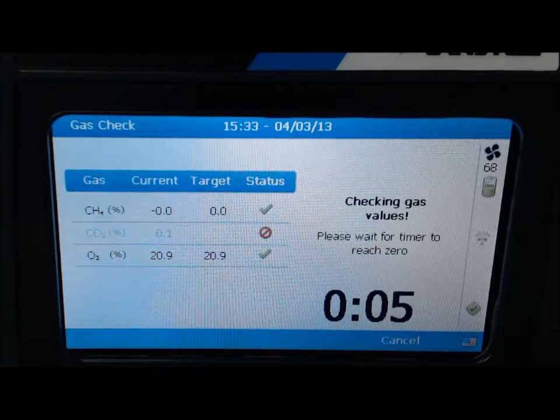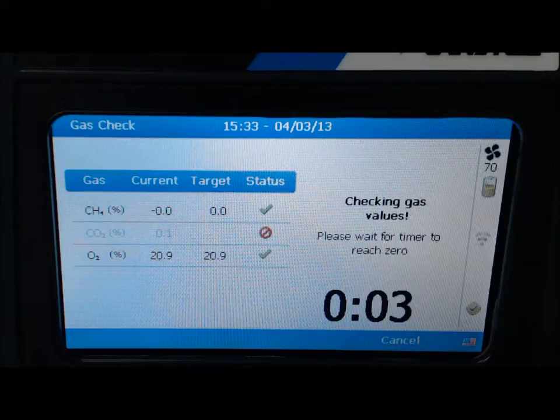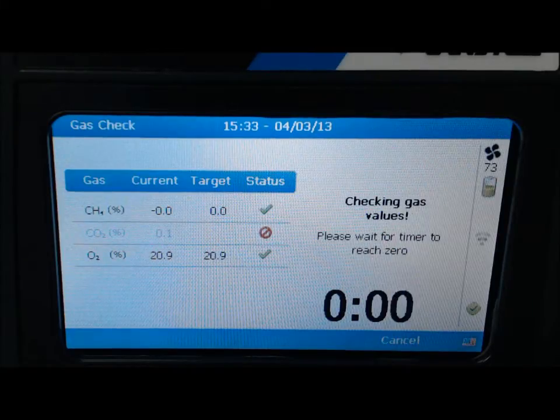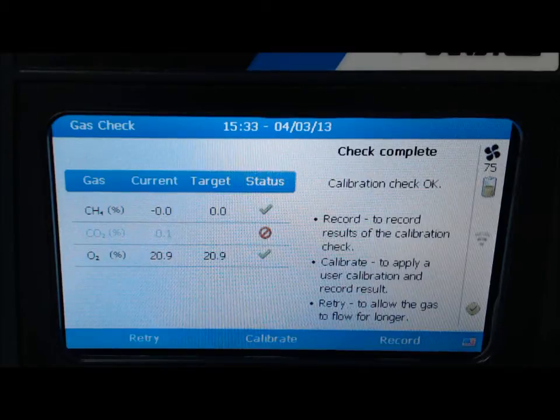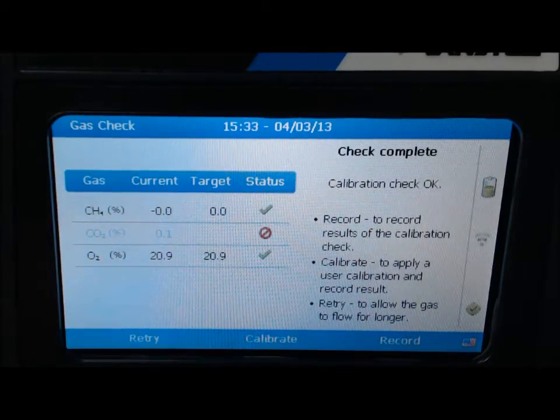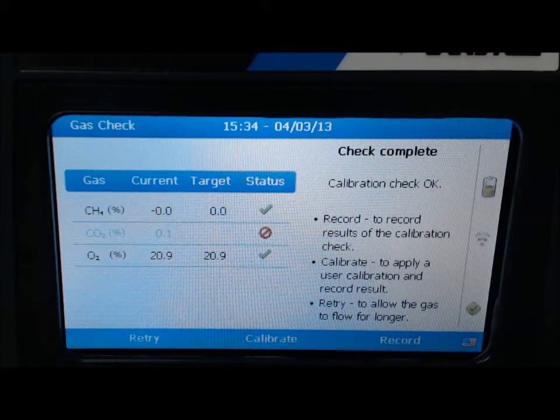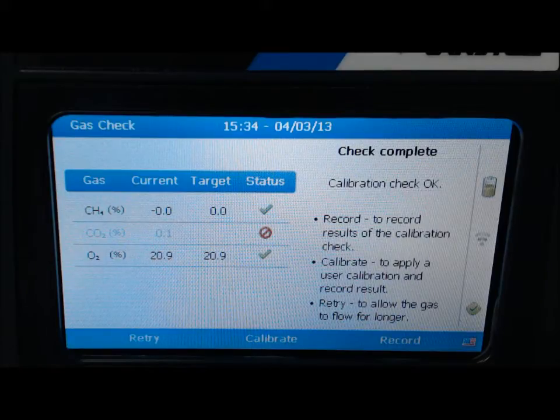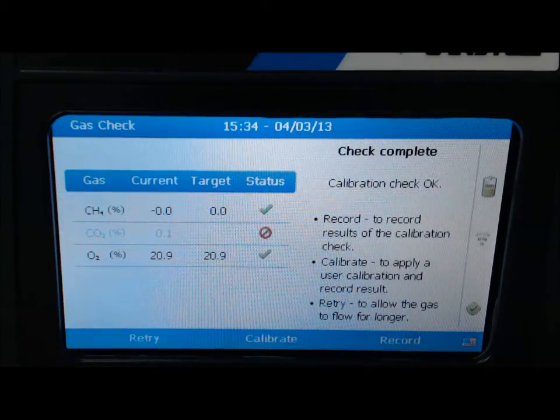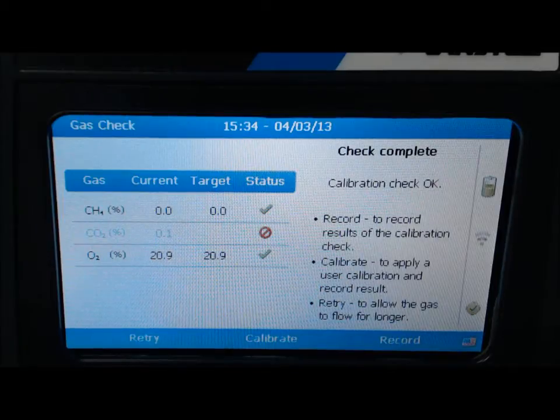When the timer reaches zero, the following messages will be displayed: Check complete. A check mark means the gas channel is within specification. The symbol next to the CO2 means the gas channel is disabled or can't be zeroed. Select calibrate to zero your CH4.